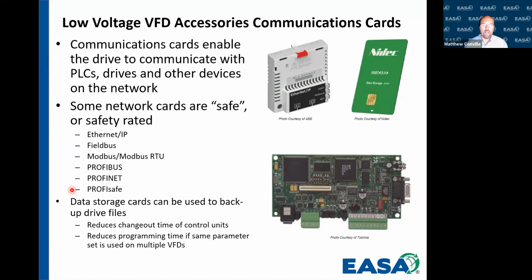One of the things that I found to be very helpful and not very expensive, but a really good time saver, was having data storage cards for the drive. A lot of drives, especially the more advanced ones, will allow you to have what they call a smart card or a compact flash card that you can store the drive's parameter set on. When these drives fail, or if we have a control unit, and these control units fail or get power cycled, sometimes they lose their parameter sets. And when they lose their parameter sets, we can upload the parameters from the smart card straight to the control unit, and you'll be back up and running very quickly.